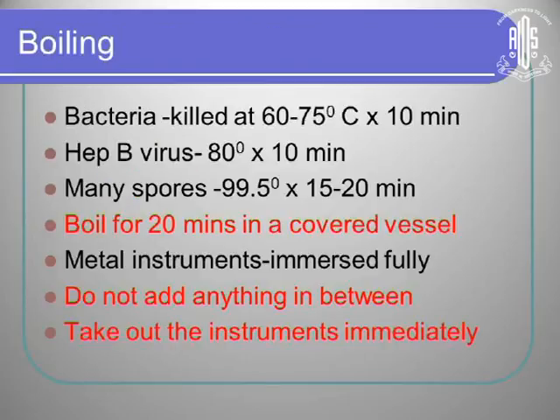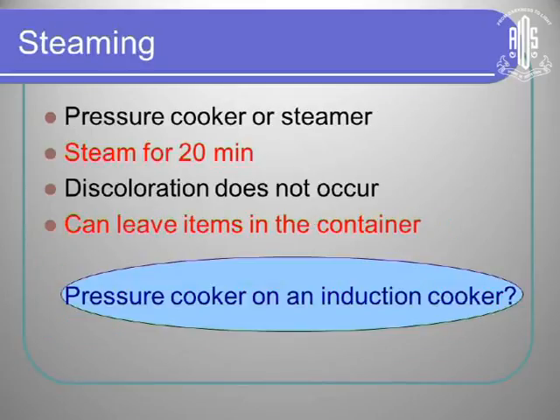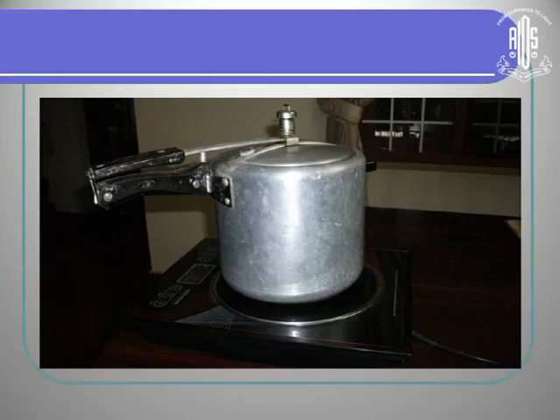If you are boiling, it has to be done for 20 minutes in a covered vessel — do not add anything into it. A common mistake is adding instruments while the sterilizer is already on — that is not proper. You must take out the instruments after 20 minutes. If you are steaming in a pressure cooker, you can leave the items in the container until you are ready to use them.